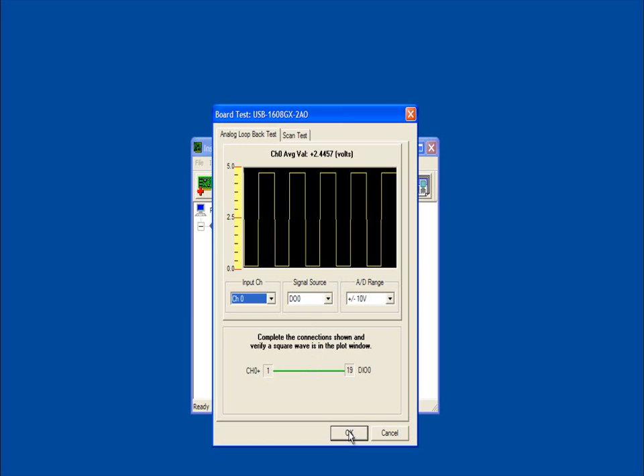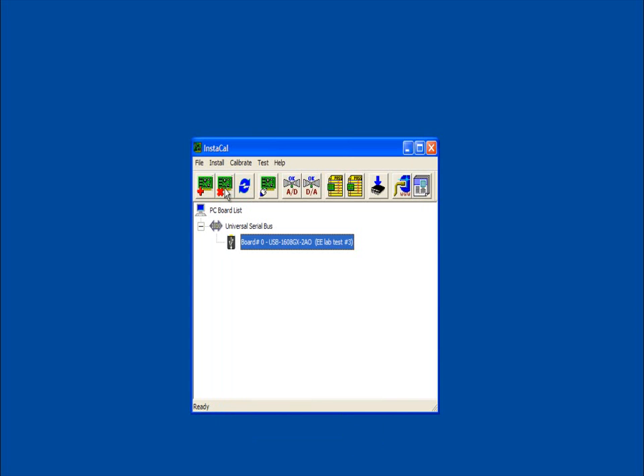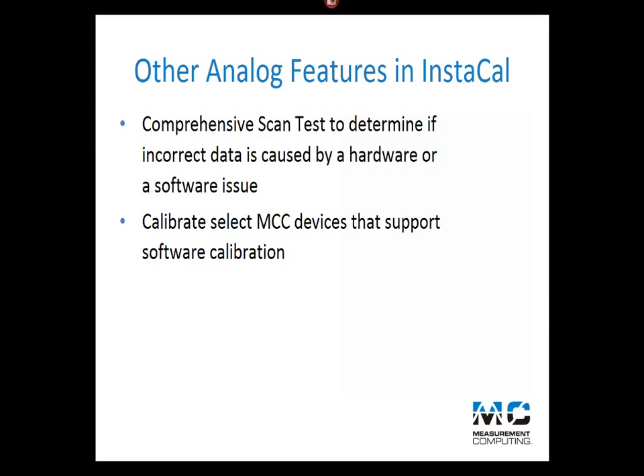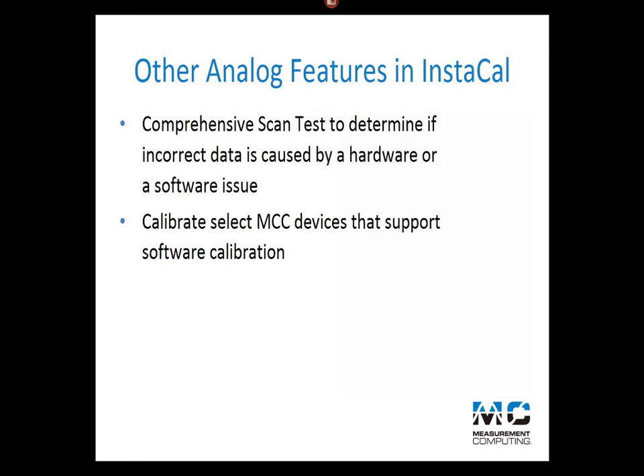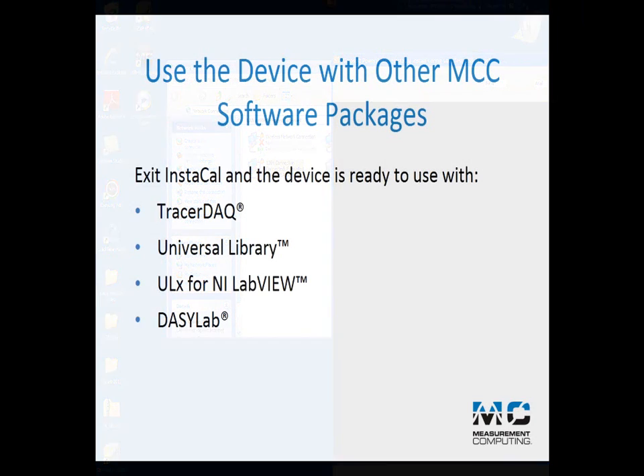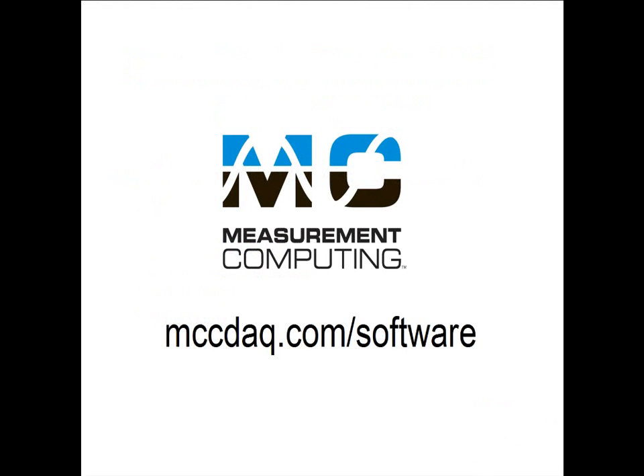When you finish installing, configuring, and testing your device with Instacal, select File Exit to close the program. Instacal also includes a scan test, which is a comprehensive diagnostic you can use to determine if incorrect data is caused by a hardware or software issue. Instacal can also be used to calibrate select MCC devices that support software calibration. Your device can now be used with other software products such as TracerDAQ, Universal Library, ULx for NI LabVIEW, and DASYLab. To learn more about Instacal and the other software packages mentioned in this video, please visit our website at www.mccdaq.com/software. Thanks for watching.